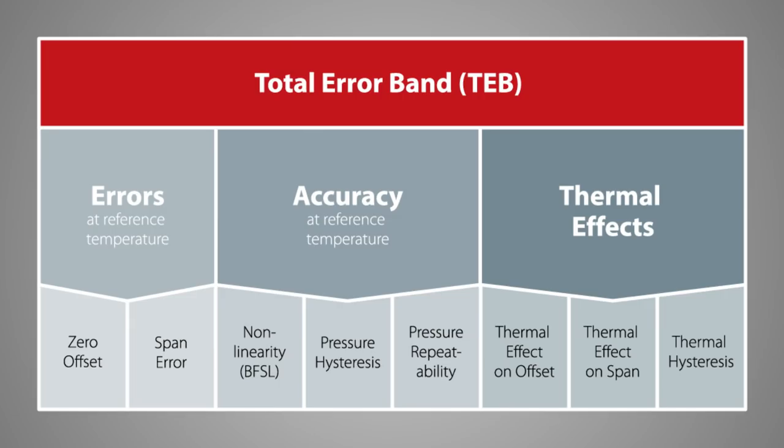These changes are not neglectable and need to be compensated to guarantee a reliable measurement at different temperatures. During the compensation process, the output signals are measured while the sensors are exposed to different temperatures in the climate chambers. The thermal effect on offset and span is calculated and mathematically compensated. It's not possible to compensate the thermal hysteresis, but we do have this influence considered in our total error band expression.